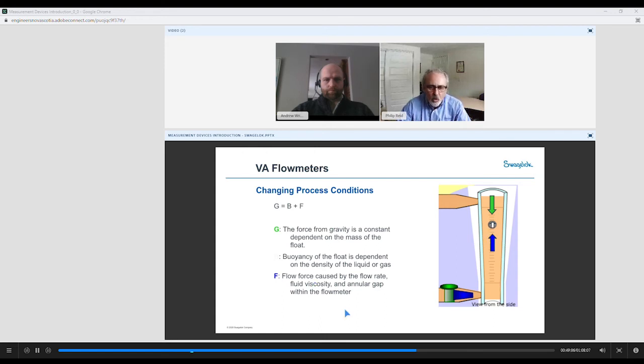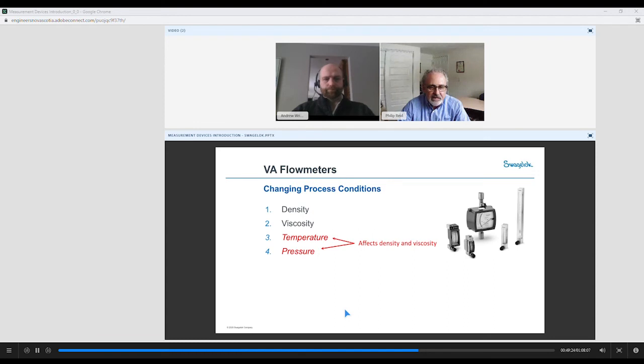Okay, so now what two things could change how this performs? I talked about how we calibrate using air and water. So if the density or the viscosity of the media change, it will change our readings if we're set for water. So what changes density and viscosity? Quite often it is temperature and pressure. So these are things that we would need to know.